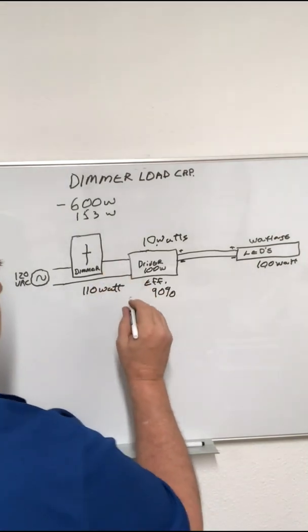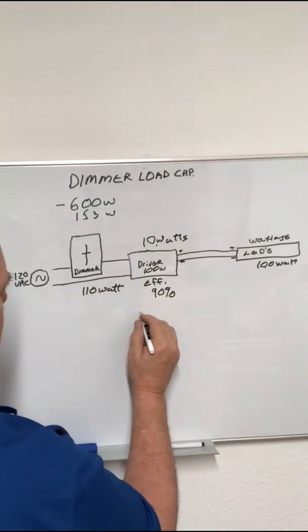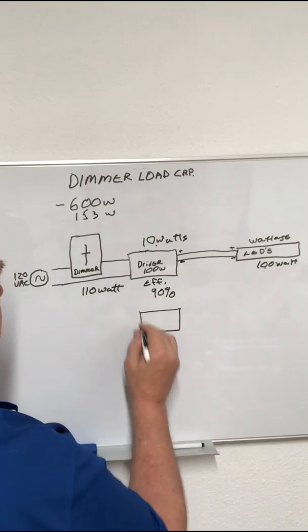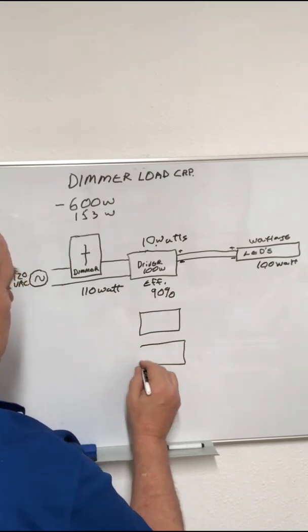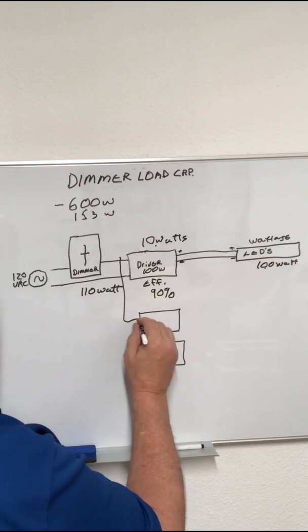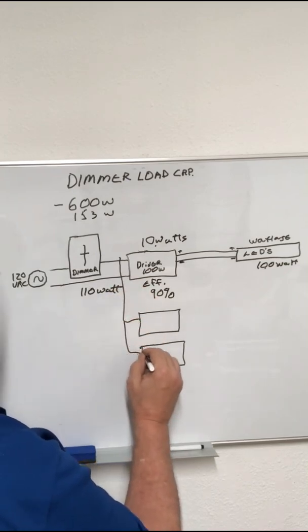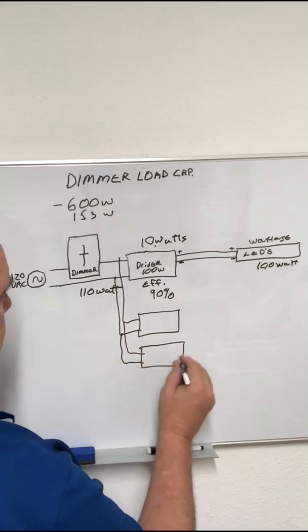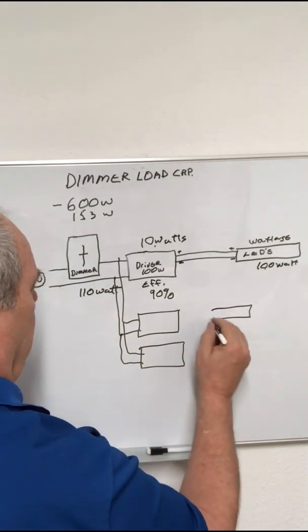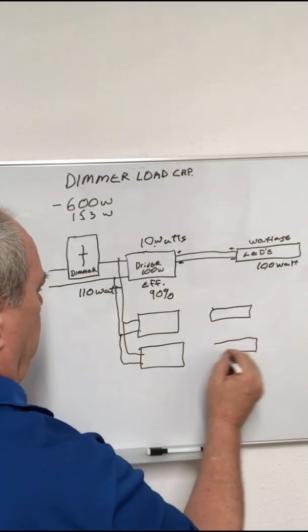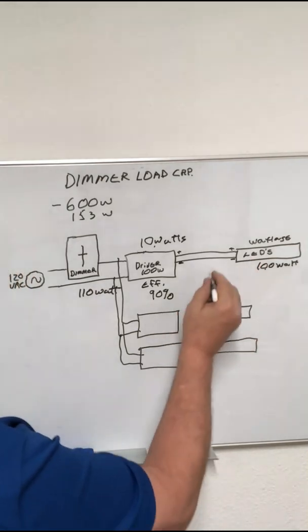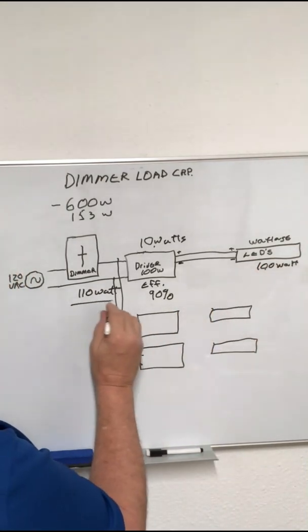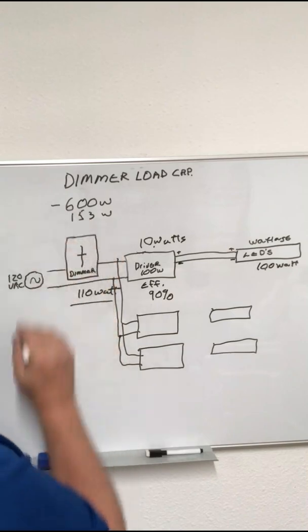But, what you have to take into consideration is if you have multiple drivers connected to the same dimmer. And then, you would have to do the calculation for each driver and load. And then, do the math, add it up, and then determine if you're still within the range.